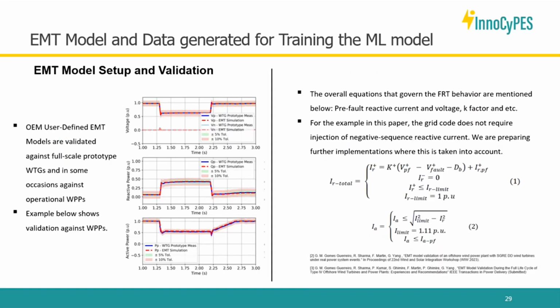Here we see a response like the one shown before during design - very flat, very easy to calculate. For example, what the injection should be based on grid code requirements for FRT. These requirements are usually written as equations like this, and it's easy to see - for a certain voltage drop, you should get a certain reactive power, so you can calculate it quite easily.